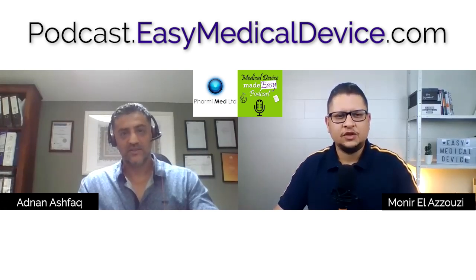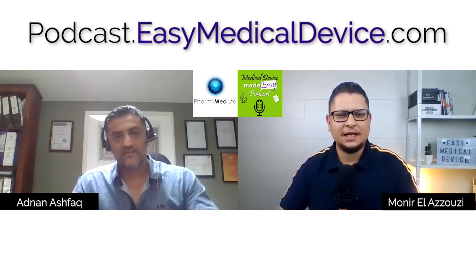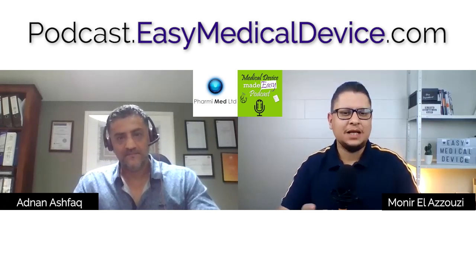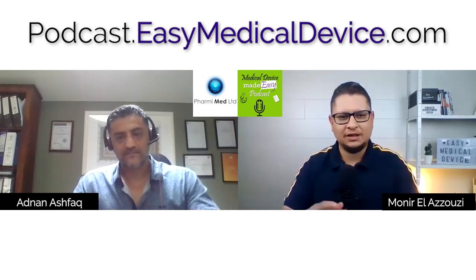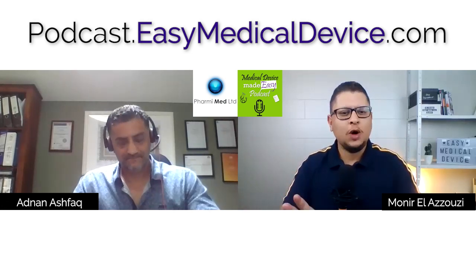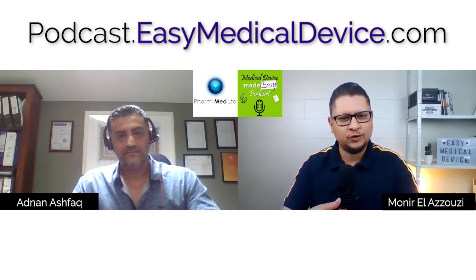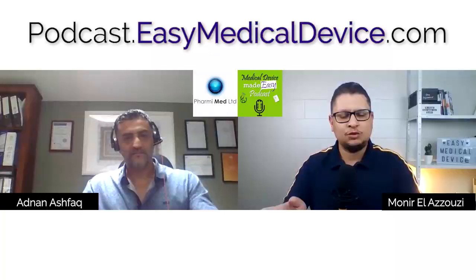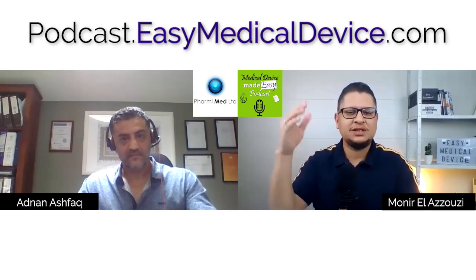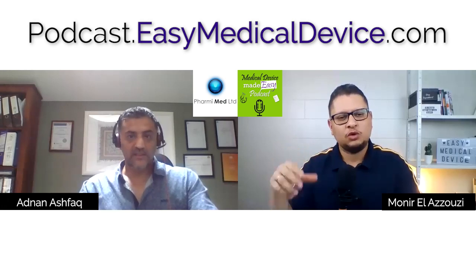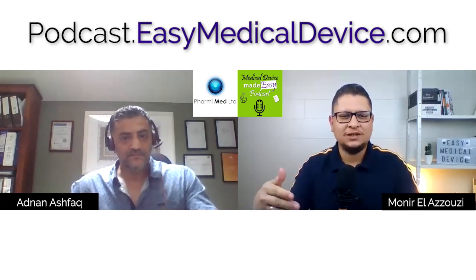Exactly. So this is what it's helping, if I can say, in terms of the classification. As we said, the classification of EU MDR and the classification of IEC 62304 do have different purposes. The one for EU MDR is to find which conformity assessment we have to follow, and the one for IEC 62304 is to find what are the processes that you have to implement for this software. Because when you look at the standard, each chapter says this chapter is for Class A, B, C, this one is for Class B and C only, etc. So it gives you which chapter, which phase is applicable. So it's really giving you different things.